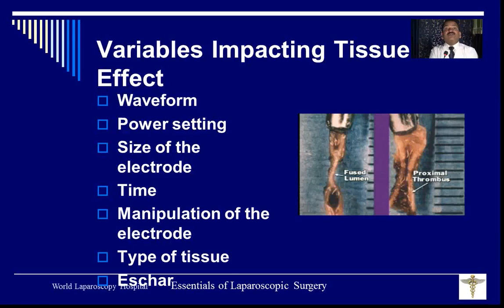Variables impacting the tissue effect. Why sometimes do we have a good tissue effect and why sometimes a bad tissue effect? These are the variables. First is waveform. You should keep in mind that the correct waveform should be used over the correct tissue. If you want to cut, if you want to blend, if you want to desiccate, if you want to fulgurate, in your machine all the buttons are there. And you should select the machine buttons correctly.